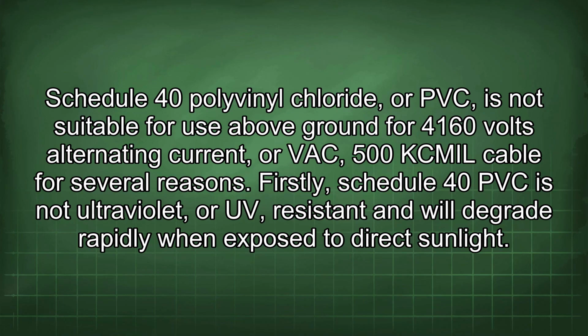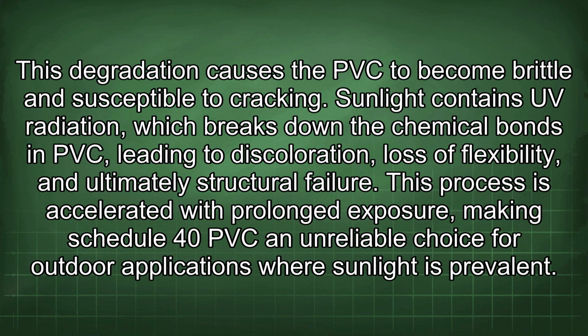Schedule 40 polyvinyl chloride, or PVC, is not suitable for use above ground for 4,160 volts alternating current, or VAC, 500 KCMIL cable for several reasons. Firstly, Schedule 40 PVC is not ultraviolet or UV resistant and will degrade rapidly when exposed to direct sunlight. This degradation causes the PVC to become brittle and susceptible to cracking.